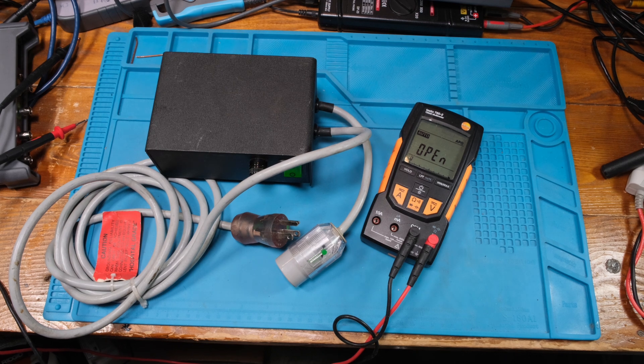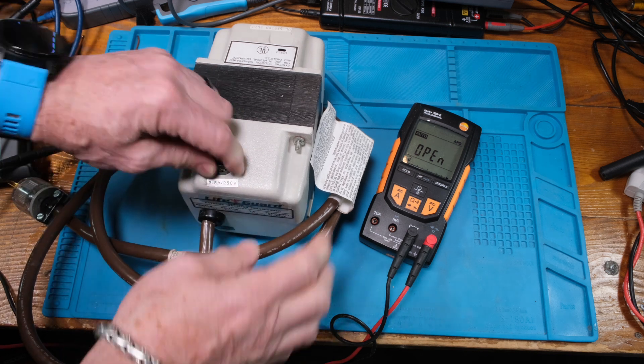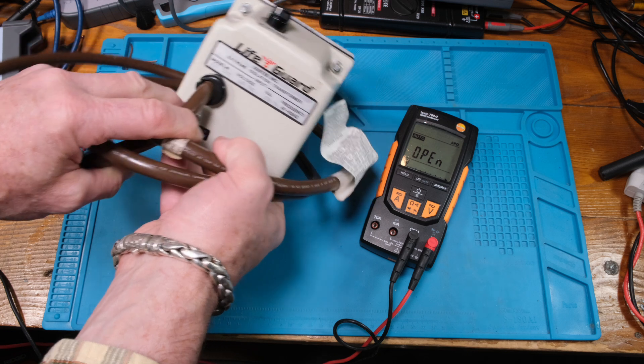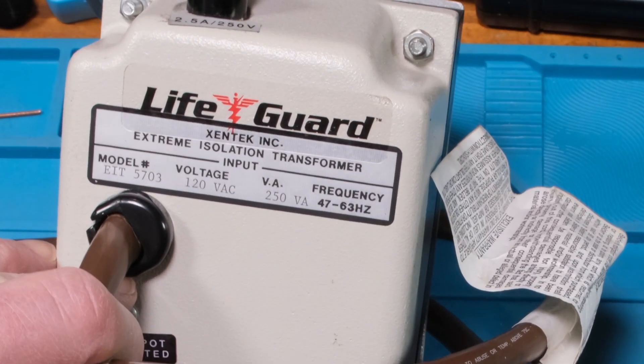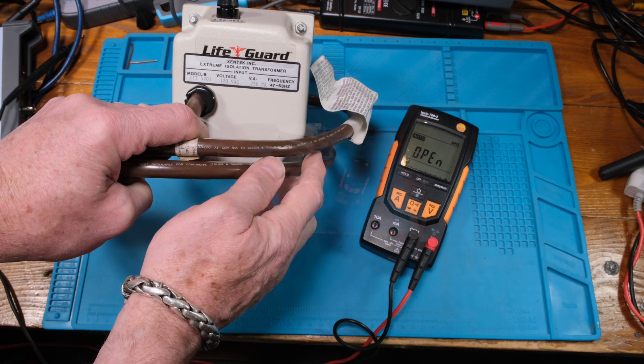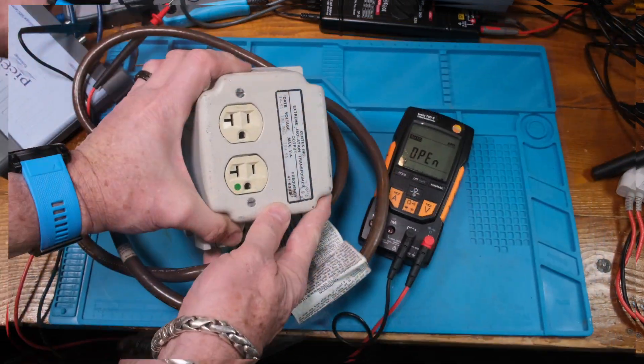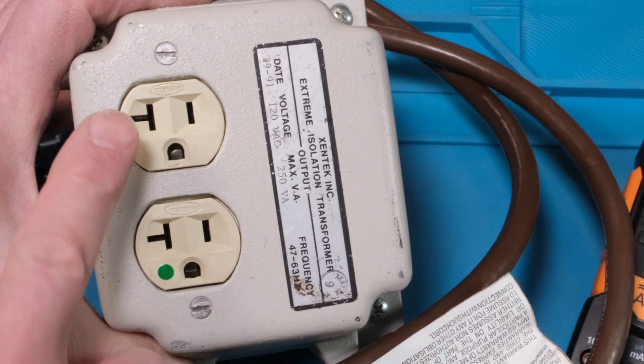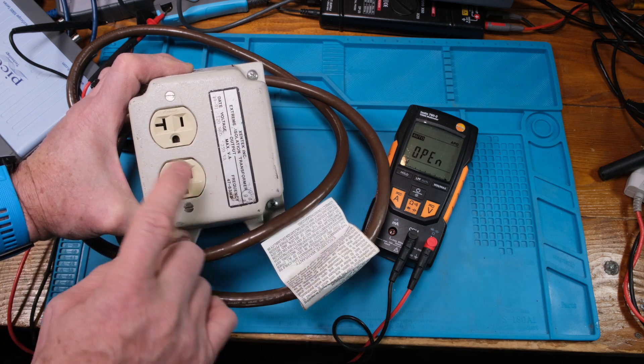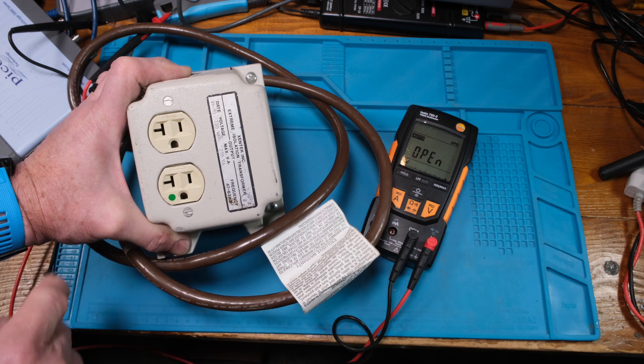Since we're on an isolation kick, let's check this one out. It says 2.5 amps — it's pretty close to the weight of the other one but a lot smaller. It's 250 VA, 120 volts. You can see it's a Xentek, high-pot tested — meaning it's isolation-tested. On this side we have two receptacles with a green dot showing it's isolated. It's dated week 39 of 1991.